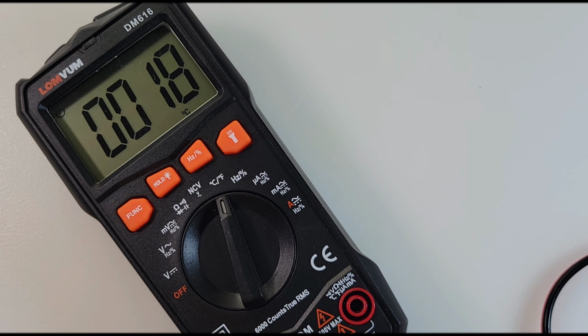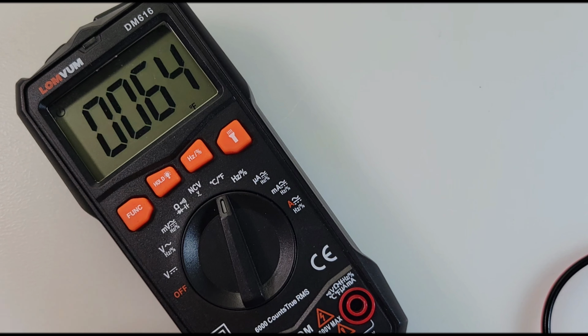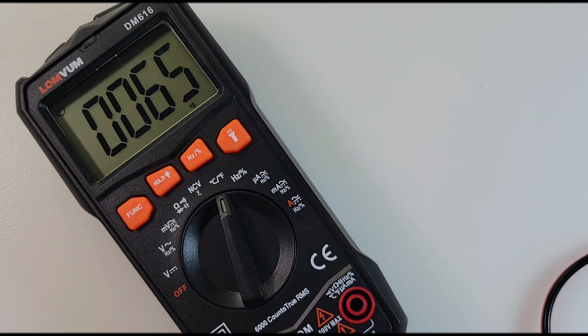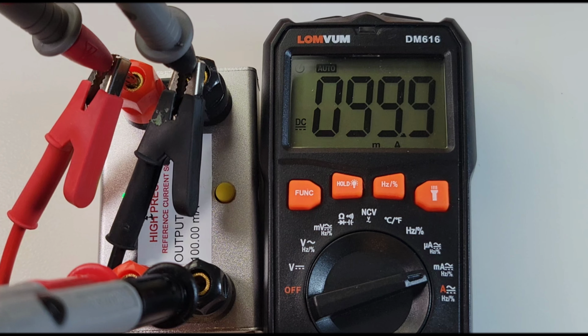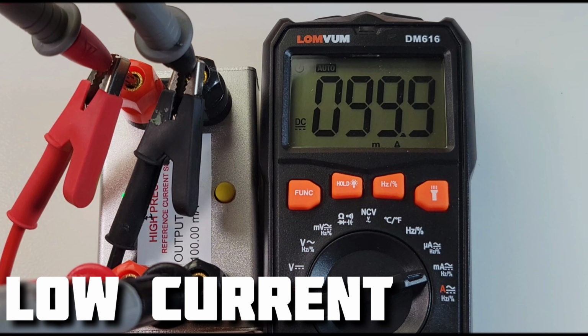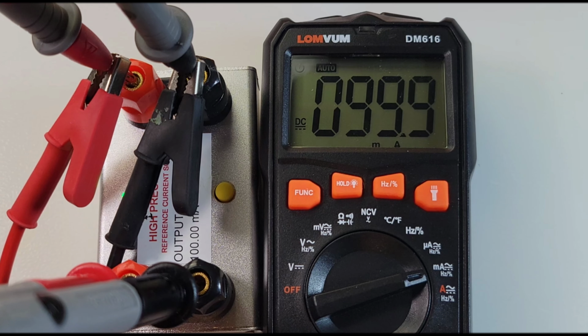In temperature mode, it has an ambient sensor on board. Always a nice thing. Hit the function switch to go from Celsius to Fahrenheit. High precision milliamp current reference, 100 milliamps. What we want, 99.9 is what we get.